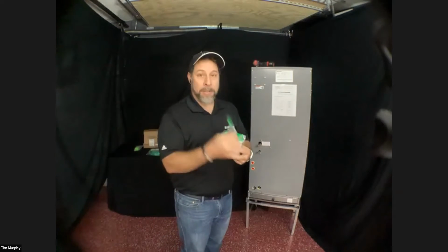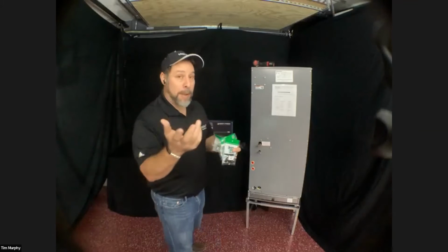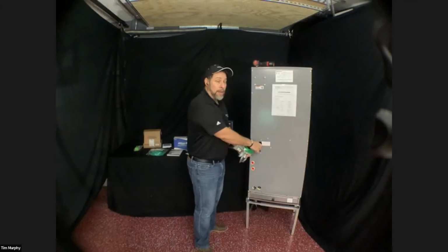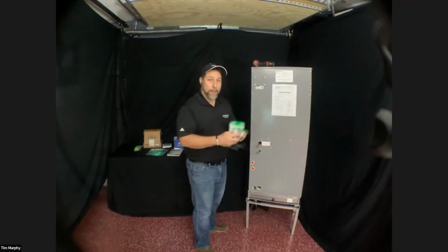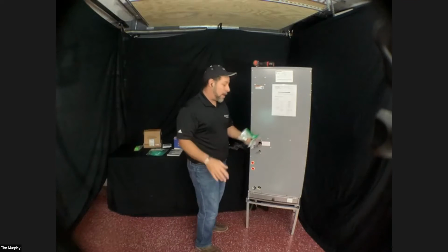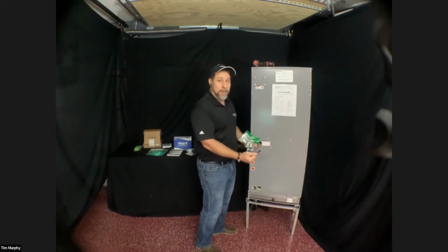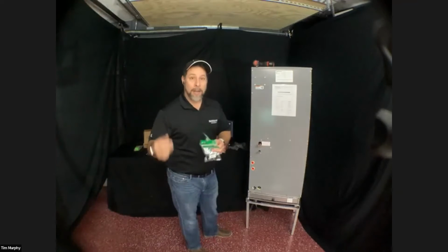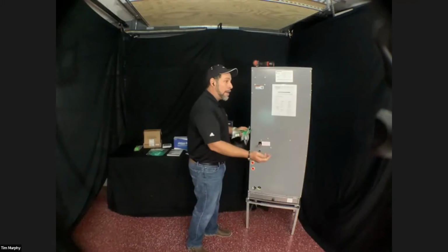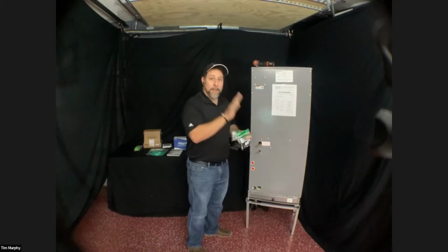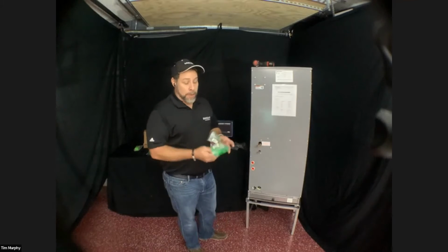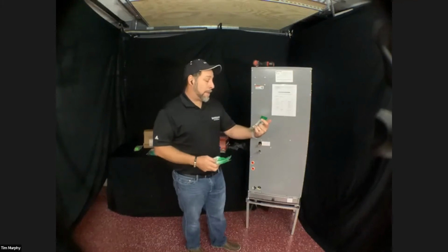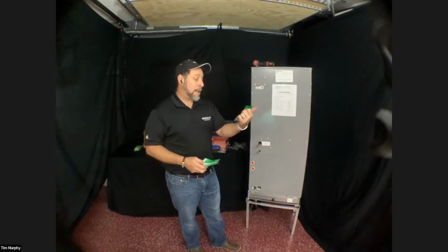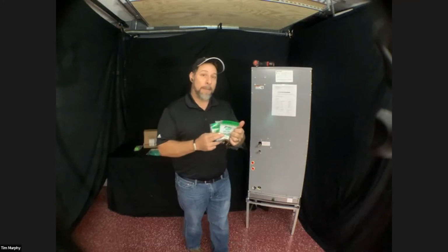I would definitely recommend purchasing the removal tool. What's great about that is if you put Zoom lock fittings on here and you need to clean a coil, if you have the removal tool, you don't need to braze at all, right? You can just use the removal tool, pop the Zoom lock fittings off, take the coil out, clean the coil, put it back in, put your Zoom locks in, put your vacuum on, and you're good to go. With the Zoom lock fittings, so far, I've been hearing great reviews, and I haven't seen anybody have any leaks as long as you do it properly.